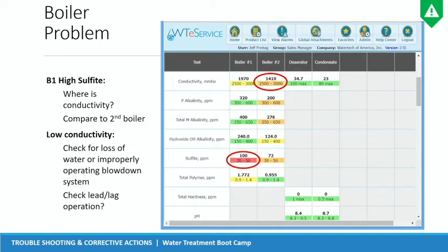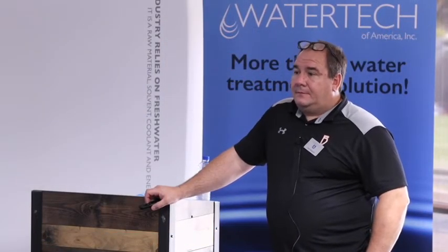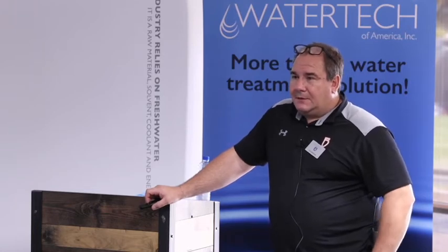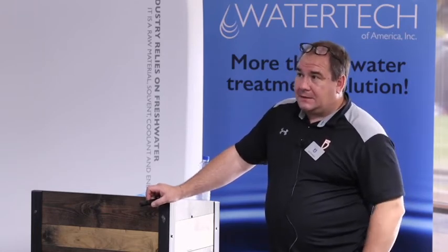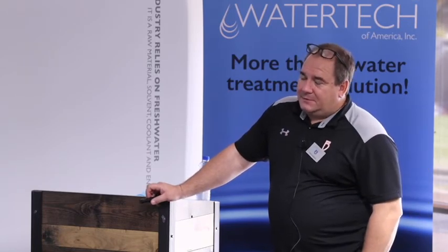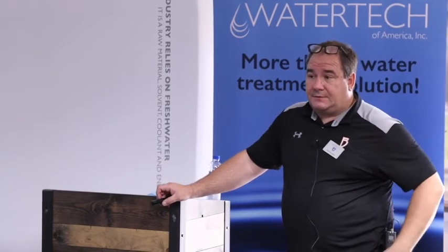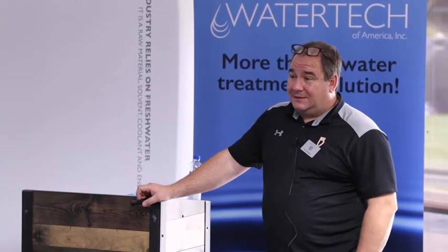And then again, you might want to check also that lead/lag operation. Maybe the set points aren't quite right. We got it at one point where we had a float and a magnetic switch on the float itself. On the shutoff? Yes. Okay. Built up sediment? Yep. We got an account one day because they had the electronic ones too, and they melted their boiler. And we got the customer then after that. But it was because of buildup in their shutoff. Yeah, it could be really critical.